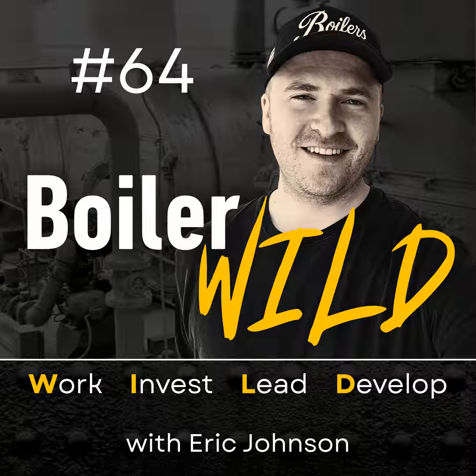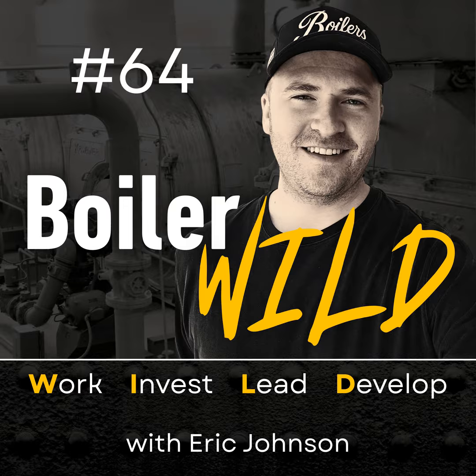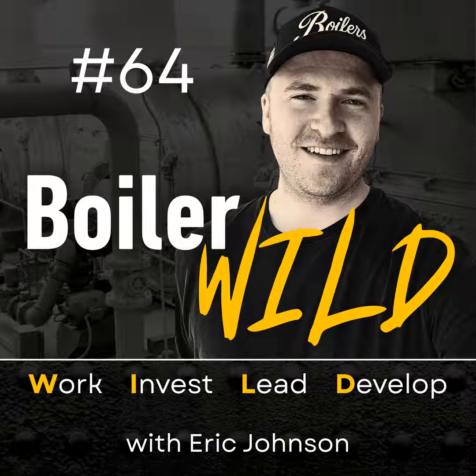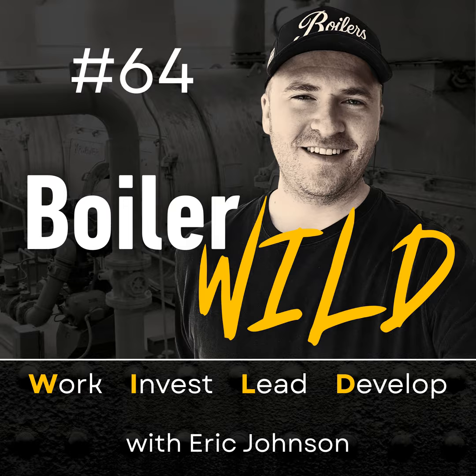Today, we're going to talk about what to do when your boiler doesn't start. This is a common problem. You can walk into a boiler room and there's no alarm. Depending on the burner control, like what is controlling the boiler burner, you can look at it and say it's the Honeywell 7800, the blue box, and it's just sitting there in standby. Yet the boiler's not running, and there's no steam pressure, or there's no hot water. An operator may be wondering, why is my boiler not running? There's no alarm. It should be running. There's no hot water. There's no steam pressure. Steam pressure is 0. Why is it not running? That can be confusing.